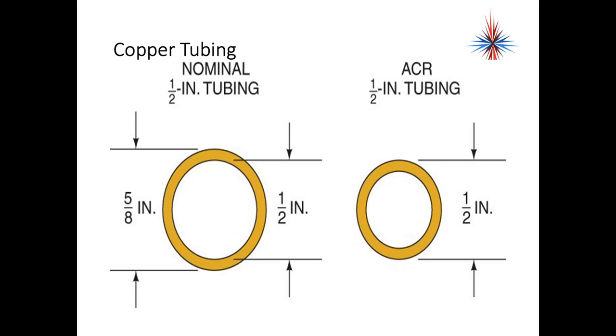If you look closely, five-eighths inches outside versus half inch inside—well, half inch is the same as four-eighths, so there's a one-eighth inch difference between the two sizes. That's for the wall of the pipe. So be very careful with tubing sizes when you're ordering. Nominal tubing is measured by inside diameter, ACR tubing by outside diameter.